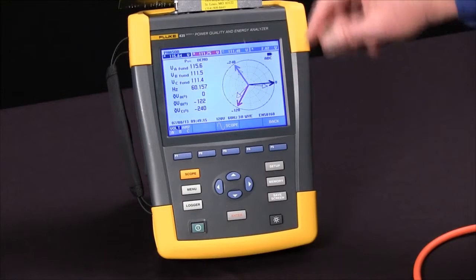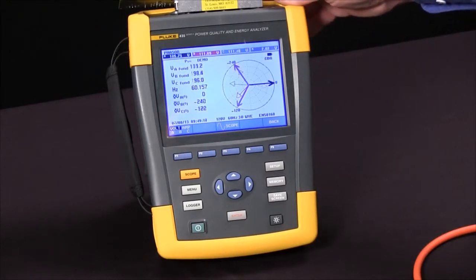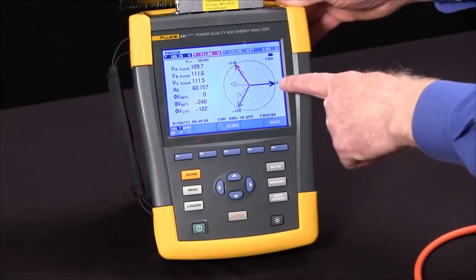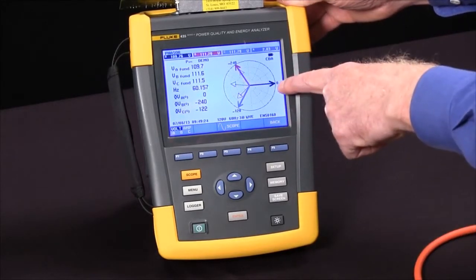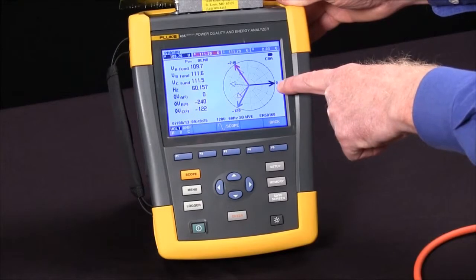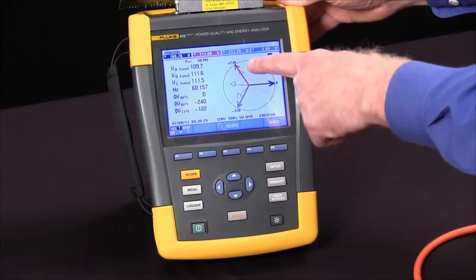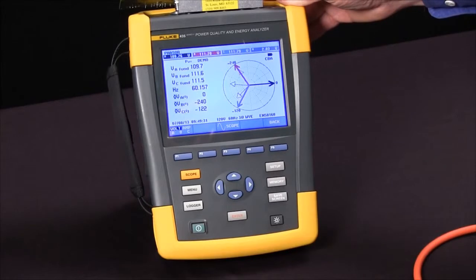If things were miswired, we might see something like this, in which case you can see your current vector for phase A is 180 degrees out of phase, meaning that current clamp is backwards, and your signals for B and C, those wires have been mixed up as well.